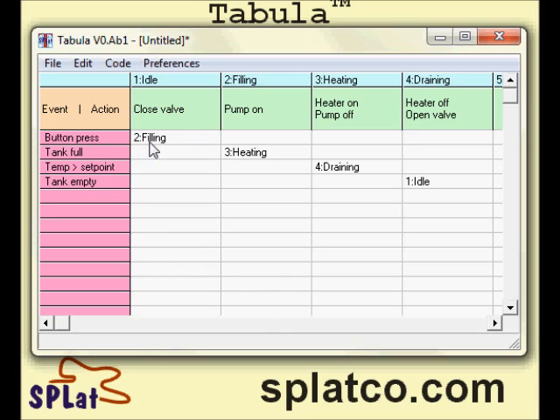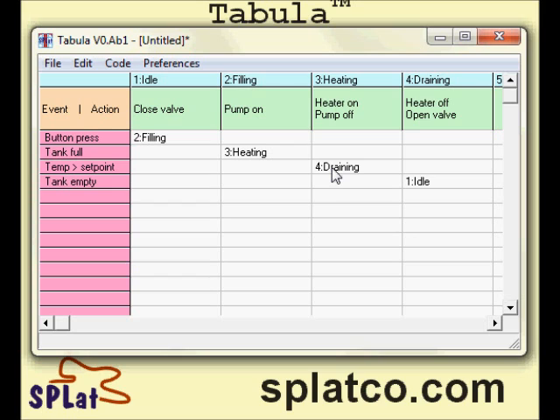The user presses the button in the idle state. We turn the pump on and sit in the filling state. When the tank is full, we switch to the heating state, where we turn the heater on and turn the pump off. When the temperature gets to the set point, we switch from the heating state to the draining state — we turn off the heater, open the valve, and sit waiting for the tank to get empty. When the tank is empty, we switch back to the idle state. That is the complete sequence. Very simple — just about anyone could read that after a brief explanation, such as watching this video clip.